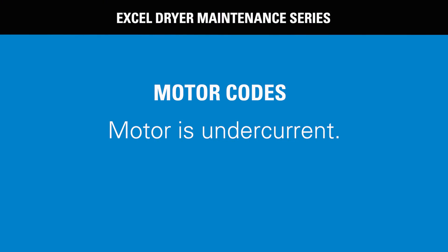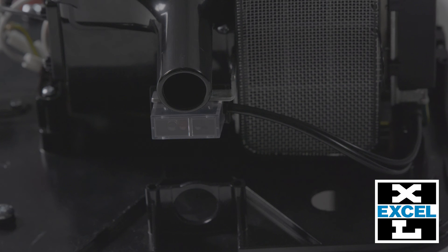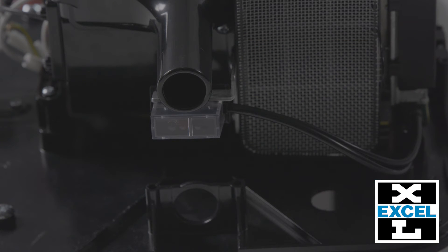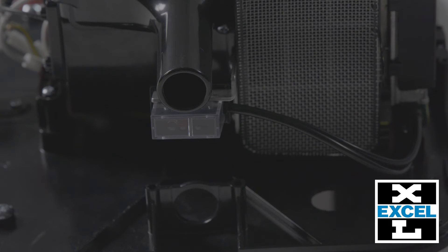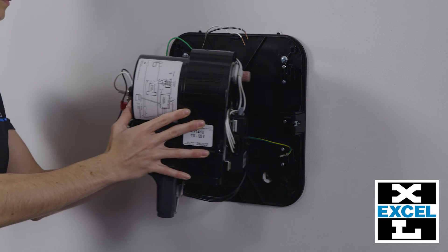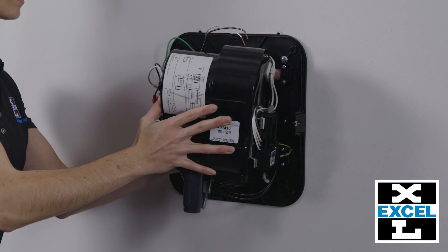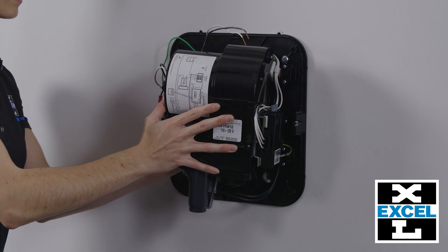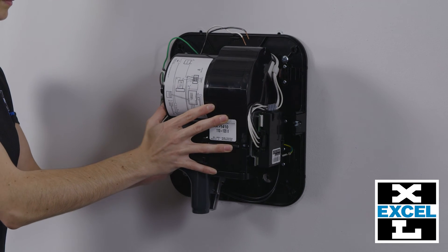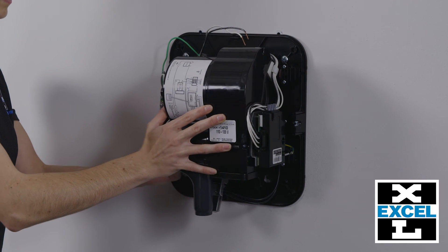Motor is undercurrent. The sensor will flash one long, four short. Again, verify the voltage, and if correct, reset the circuit breaker. If problem is not resolved and the motor wire is not disconnected, replace the motor.